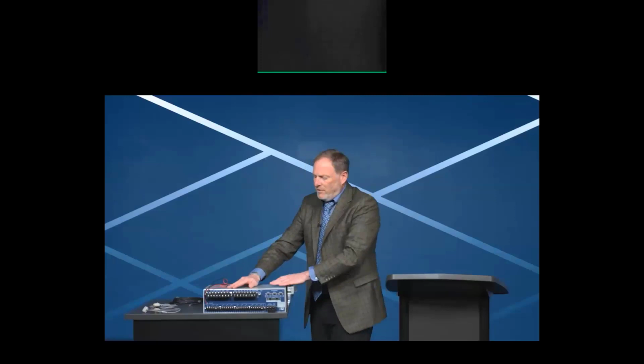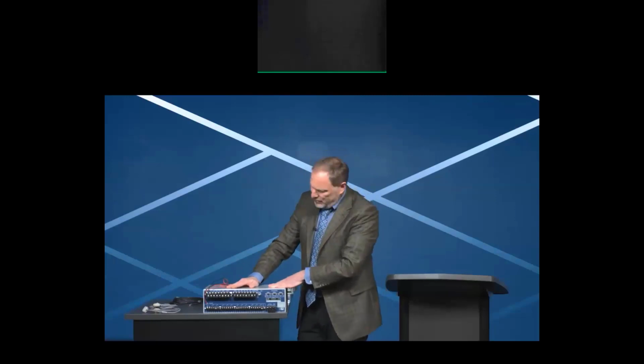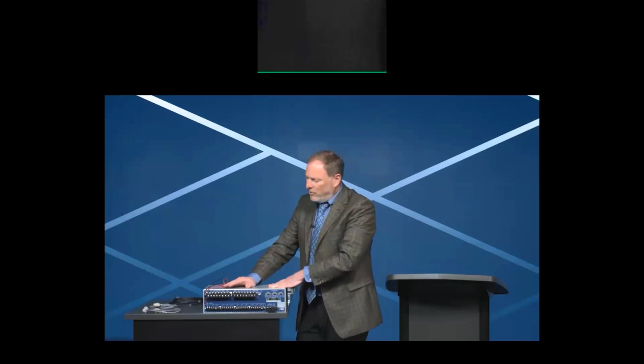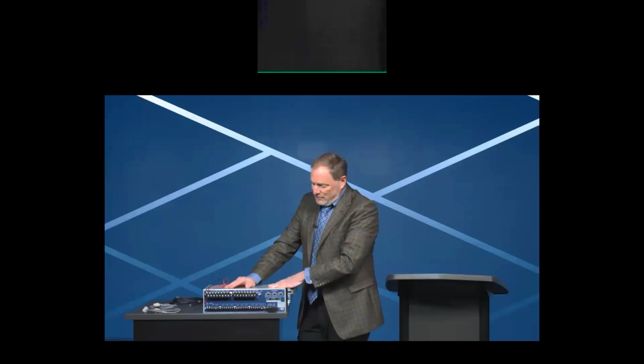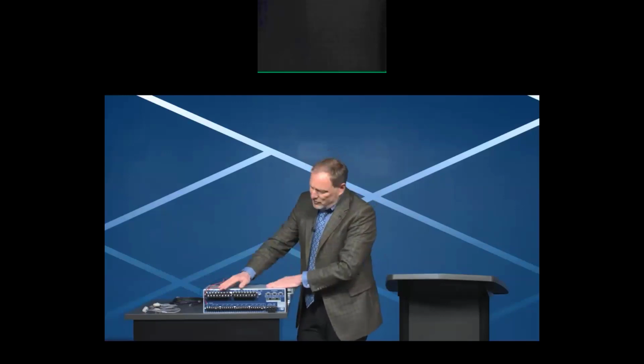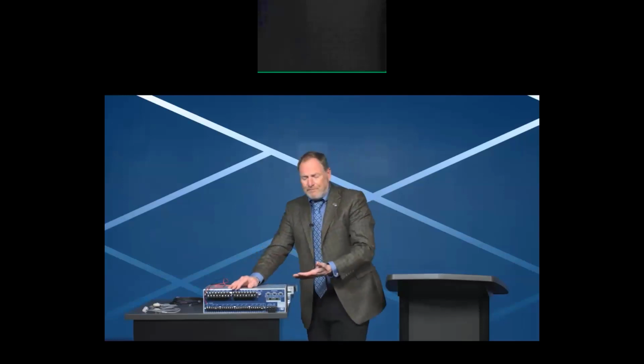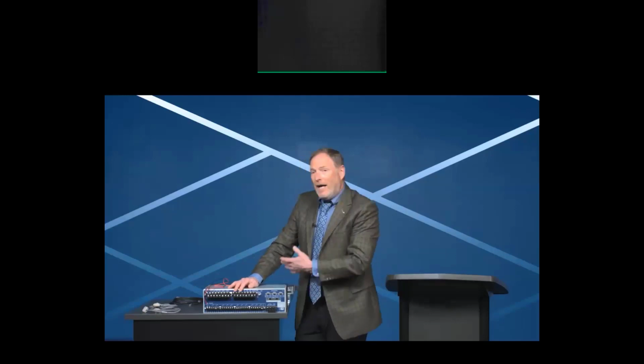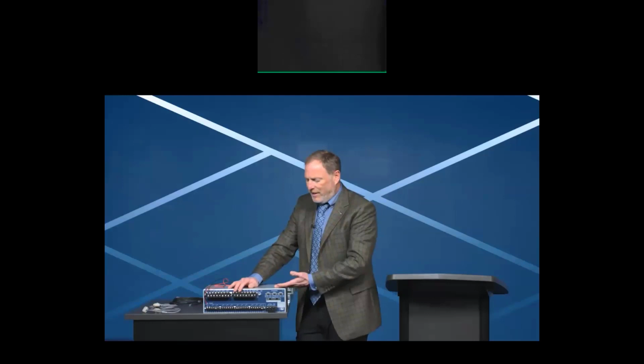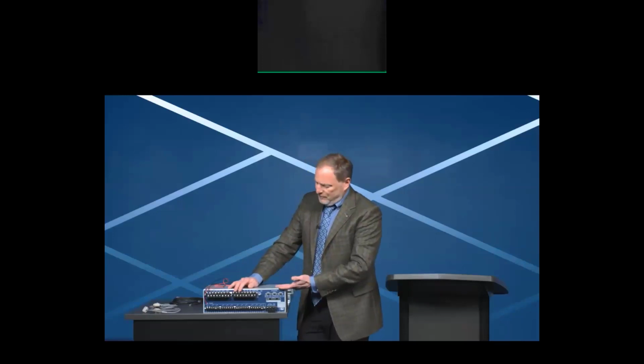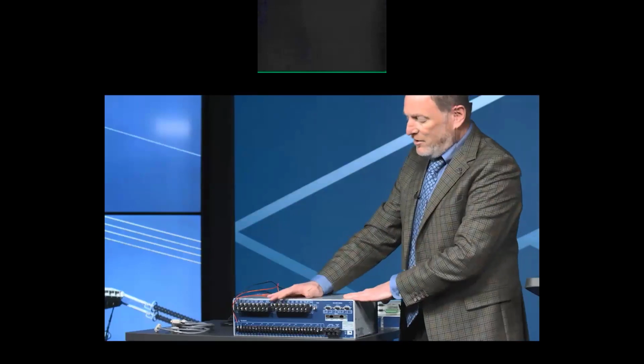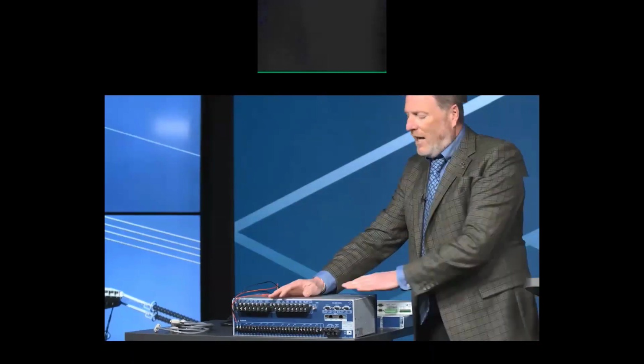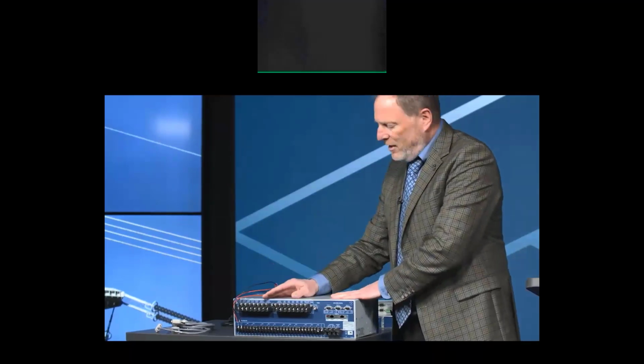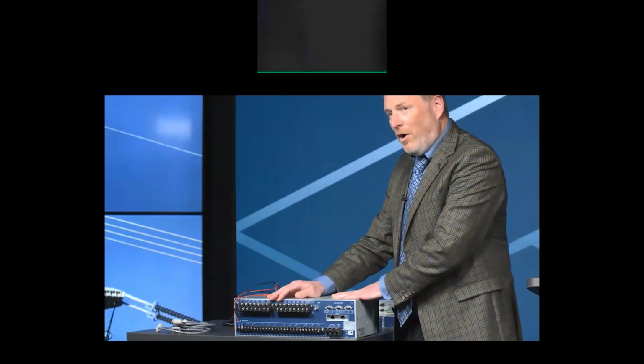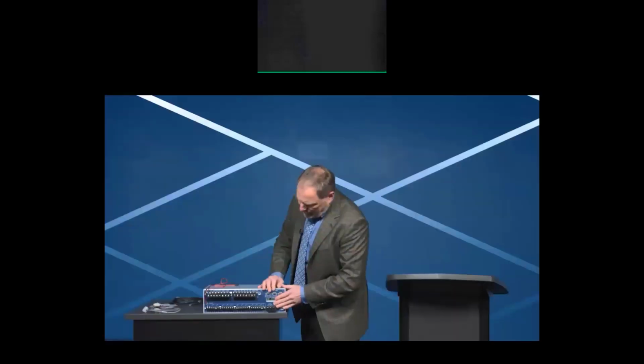The reliability of this card is determined by the failure rate in service. Over the past 10 years, we've had 136,790 of these boards installed and in service. And over that time, we've had 59 reported failures. Now, many of those, if not most, were actually customer-induced failures where they fused the contacts together by trying to break excessive current, well beyond what's recommended in the instruction manual. However, we don't care. We count all of those failures. And counting those, we come up with an MTBF, or a mean time between failure, of 23,183 years. Now, that doesn't mean that I expect this card to be in service for 23,000 years. What that means is I expect if you have 23,184 of these boards in service for a year, that you can predict that one or fewer of them will fail in service.